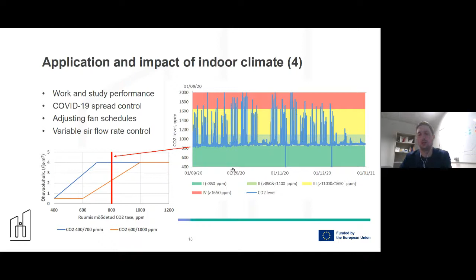We've also seen, in the same example with an 800 ppm base level, that when you have a variable air volume or demand controlled ventilation system, the control principle is often that airflow rate changes linearly between a minimum and maximum CO2 set point. If the measured value never goes below 800, depending on the set point, you can very easily over-ventilate a room when the air handling unit is working, and this wastes energy. I believe there's a huge energy saving potential here. Luckily, or unluckily, this building has no VAV ventilation.